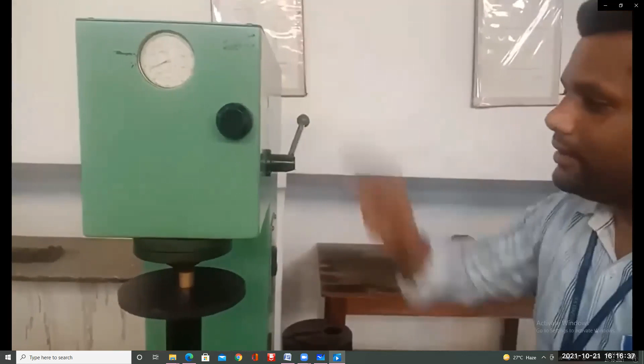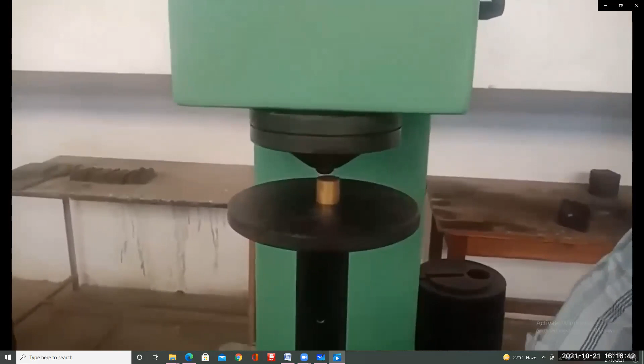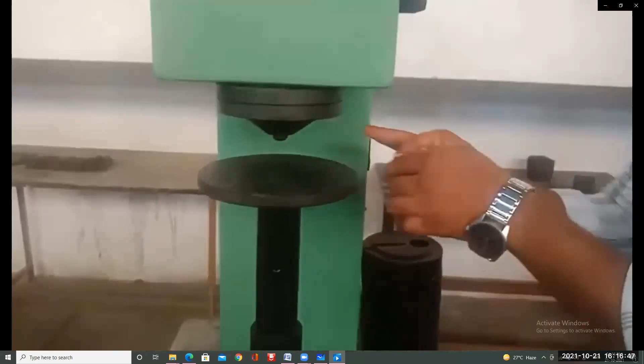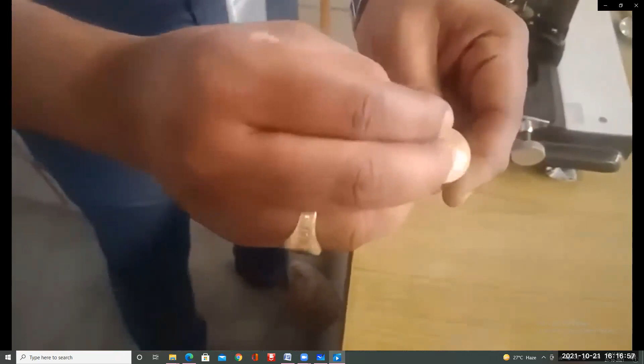Once it stops, we release the load. Then we take out the specimen. After 5 minutes, release the load. Then, in anti-clockwise rotation, we retract the anvil, take the specimen and switch off the machine. Then an indentation mark should appear on the specimen. With the help of a chalk piece, we mark that.